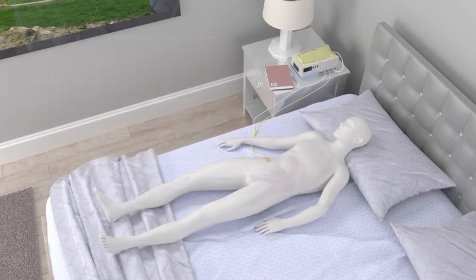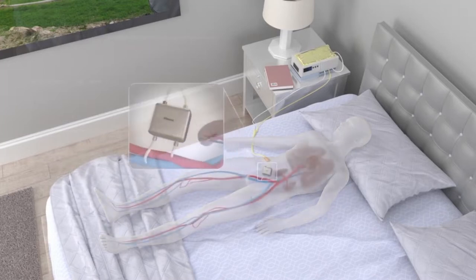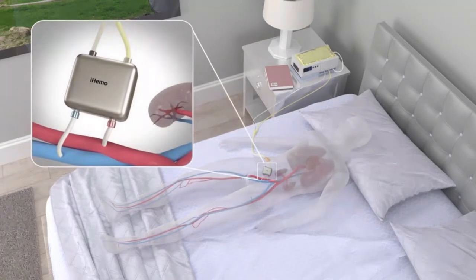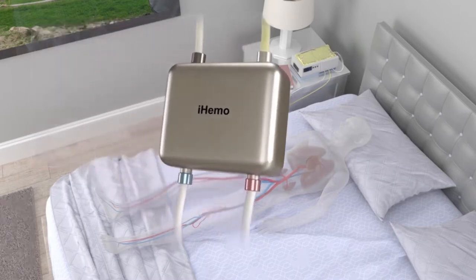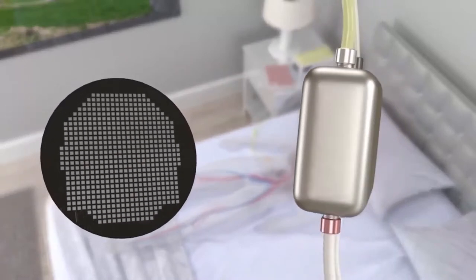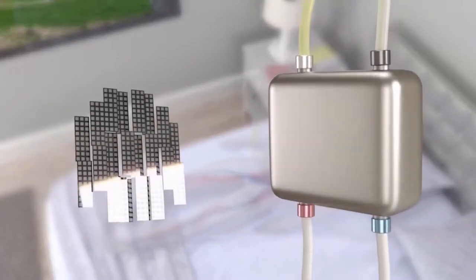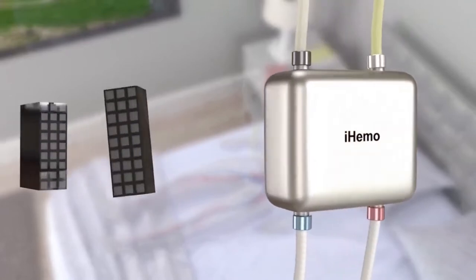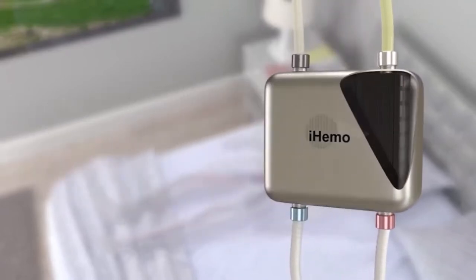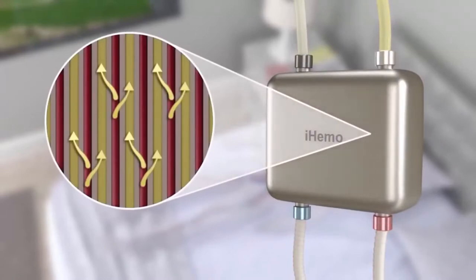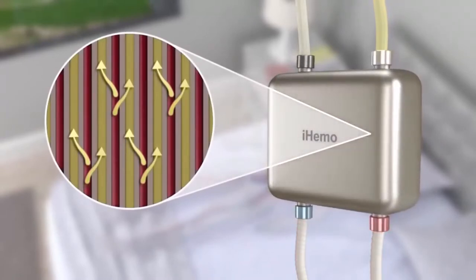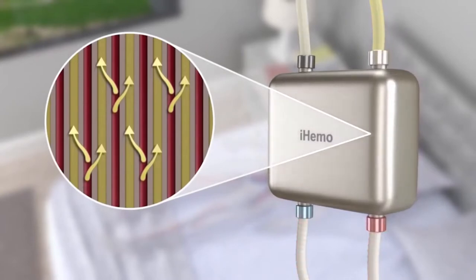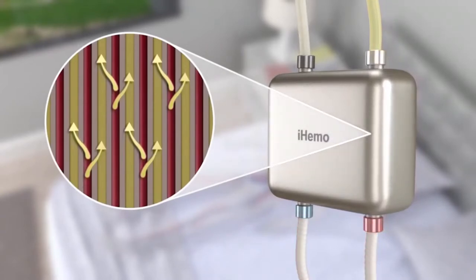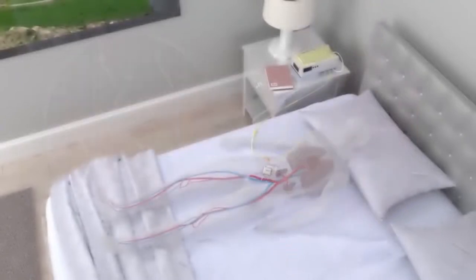In the iHemodialysis system, the hemofilter is surgically implanted inside the patient's abdomen. The hemofilter connects to the circulatory system on one side and on the other side to catheters leading to a small external pump. Inside the hemofilter are highly efficient biocompatible blood filtration membranes, made possible by advances in silicon nanotechnology. Because the membranes are compact, the hemofilter is small enough to implant. The patient's heart pumps blood through the hemofilter, while the external pump sends dialysate into the hemofilter and carries away toxins and excess water.